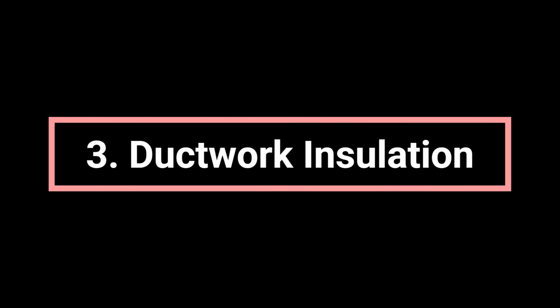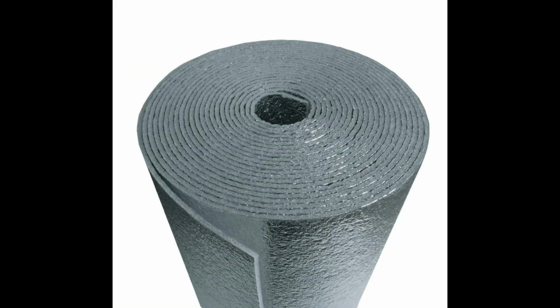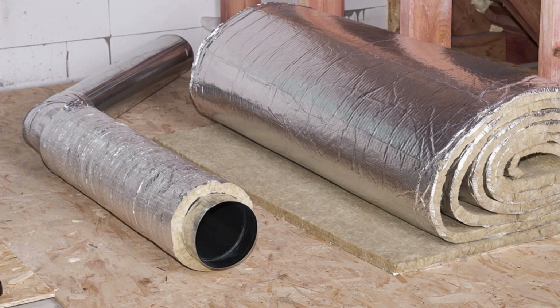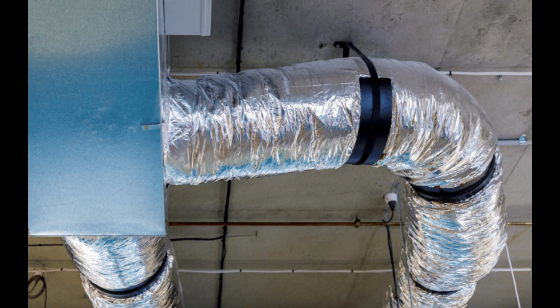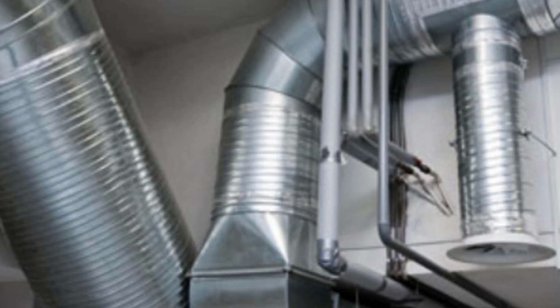Number 3. Ductwork insulation. Correct insulation is essential for enhancing the thermal performance of ducts. According to ASHRAE 90.1-2019 guidelines, insulation helps prevent condensation and dripping by maintaining the desired temperature of the air being transported. Uninsulated ducts can lead to energy wastage as additional heating or cooling would be required to achieve the designed supply air temperature. Insulating ducts eliminates the formation of condensate, preventing potential water damage and microbial growth within the building. This is particularly important for maintaining the integrity of the HVAC system and ensuring indoor air quality.